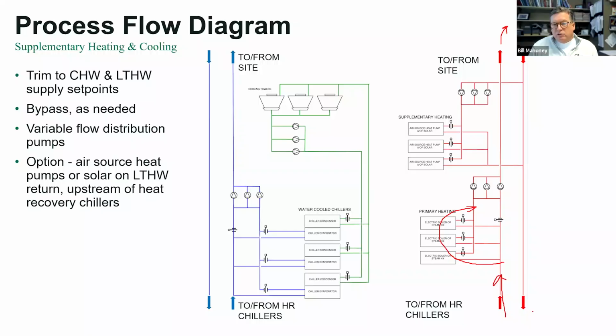And that's because these are air source heat pumps. So they have trouble, as you said, Alex, when it's 0 degrees outside. You might have trouble making 140-degree water. So we let them see the 110-degree water coming back, and maybe they can only get it out to 120 or 130. But then we pass it on, and the heat recovery chillers can do the rest for them. So these are specifically arranged so that the warm 110-degree water first hits air source, then ground source, and then the traditional. Get what you can, and when you haven't made it all, make up the difference with the traditional.